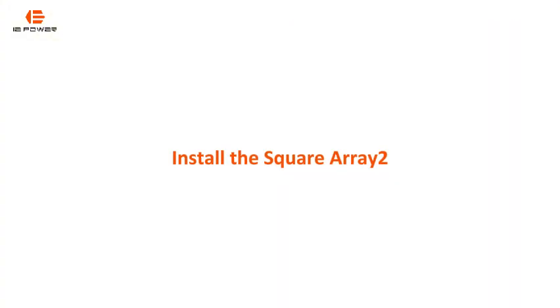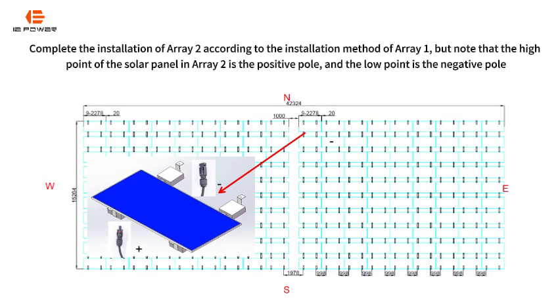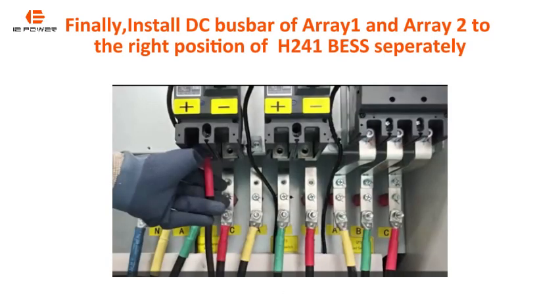Install the square array 2. Complete the installation of array 2 according to the installation method of array 1, but note that the high point of the solar panel in array 2 is the positive pole, and the low point is the negative pole. Finally, install DC busbar of array 1 and array 2 to the right position of H241 BESS separately.